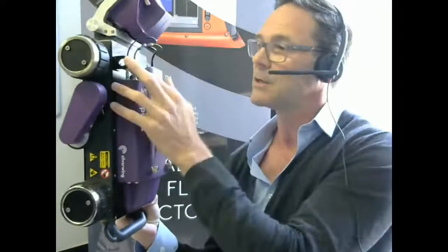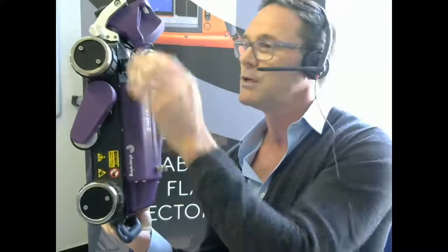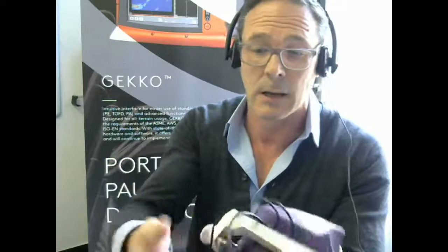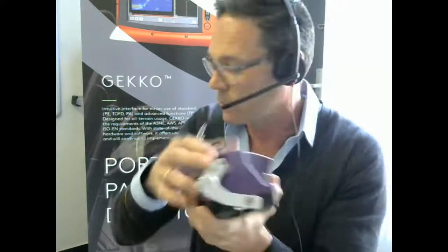This is the probe head, like I said, and it's very simple to detach that probe. We have these 2 pull levers on each side, and if we pull that lever, we can quickly disconnect that probe head in a matter of minutes, which is quite good because it helps us to do maintenance on the probe head quite easily. And there we go. Probe head is off. We now have full access to the wheel probe for maintenance, for cleaning. These are wear shoes that we can take off quite quickly. And for reconnecting it, we just have to connect the plugs.